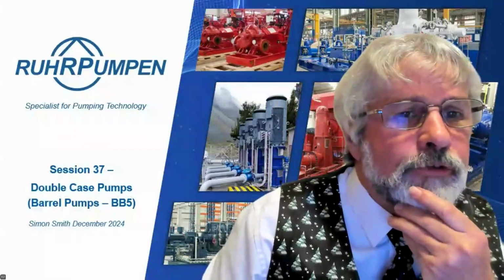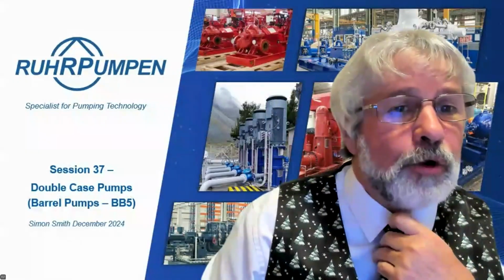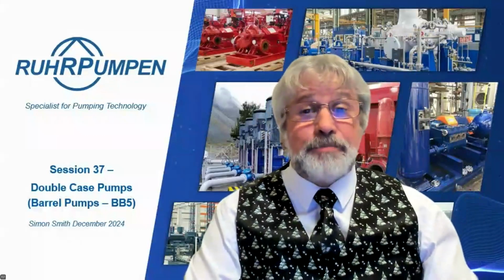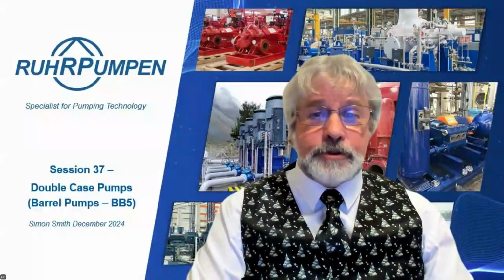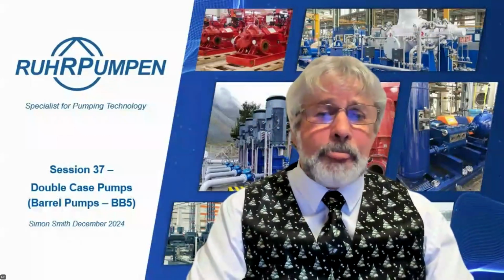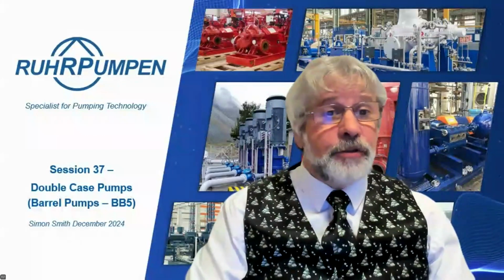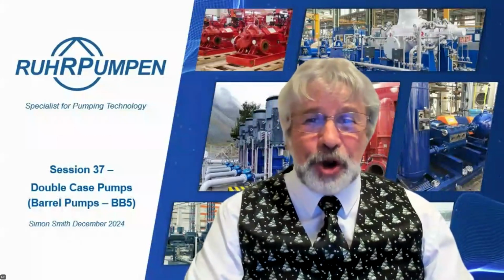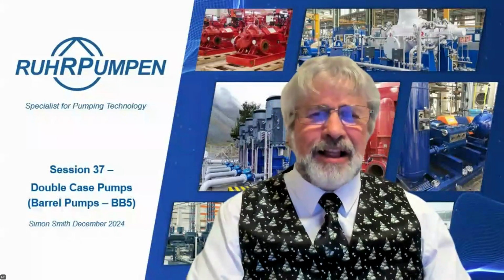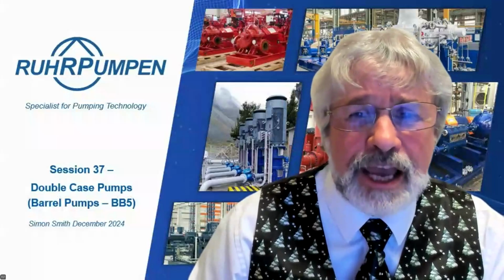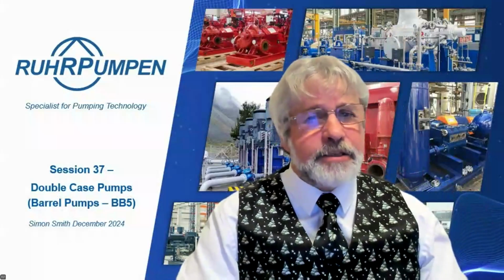Jeroen Boller says, do you have any experience with pitot tube type pumps for low flow, high head applications? Yes, we have some pitot tube pumps. It could be considered as an alternative to the OH6 pump, if you like. It might be a good idea to consider doing a presentation on those pitot tube pumps. There's something completely out of the ordinary. Not many people know about them, in fact. Yeah, I'll write that one down for the future. But we do have a pitot type. We call it the combi tube, and it's good for up to about 50, 60 cubic meters an hour, and pretty high heads. I can't remember exactly, but it is good for that in clean service.